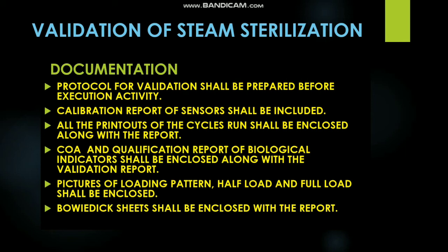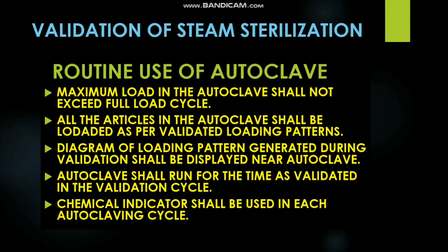The pictures of the loading pattern, half load and full load, shall be enclosed along with the diagrams generated during your qualification activities. Bowie-Dick sheets or chemical indicators which are used need to be included along with your validation load. Then the precautions which need to be followed during routine autoclave use are specified over here. The maximum load in the autoclave cycle shall not exceed the full load cycle.